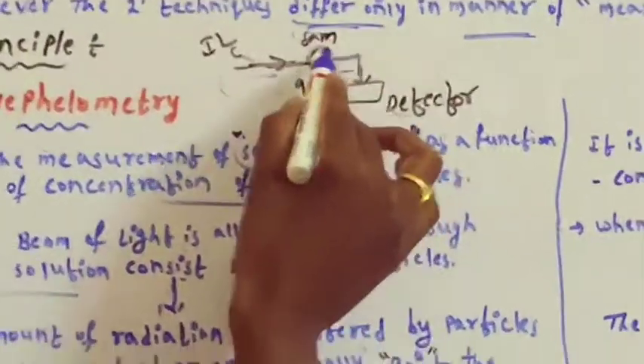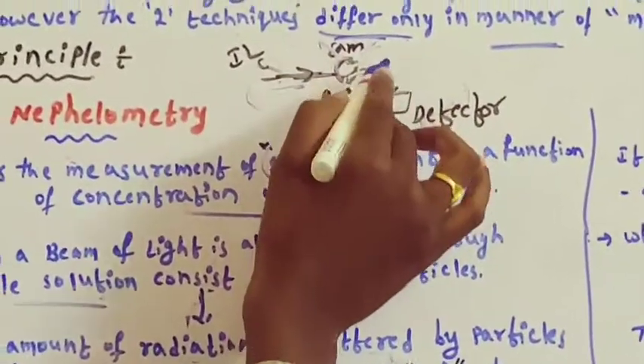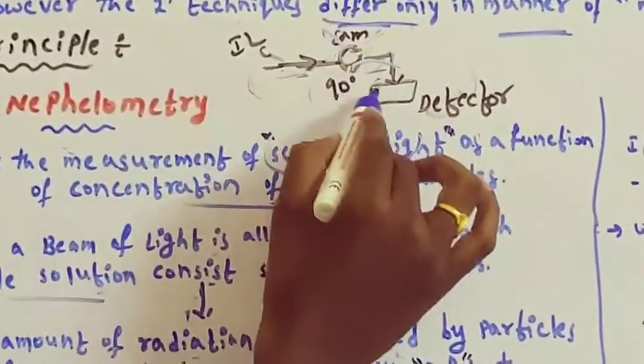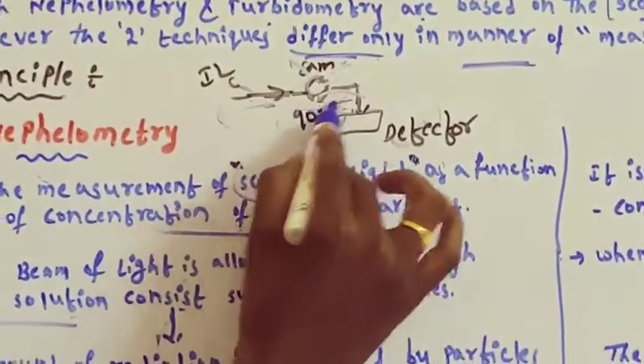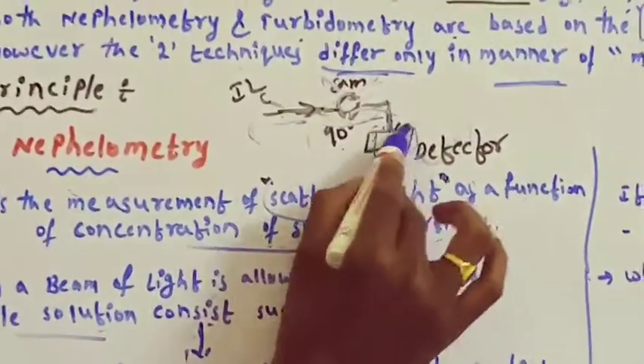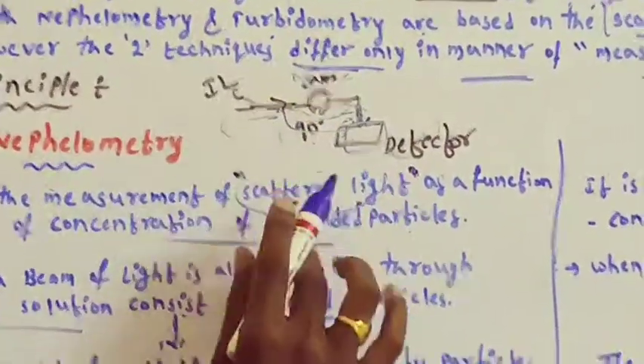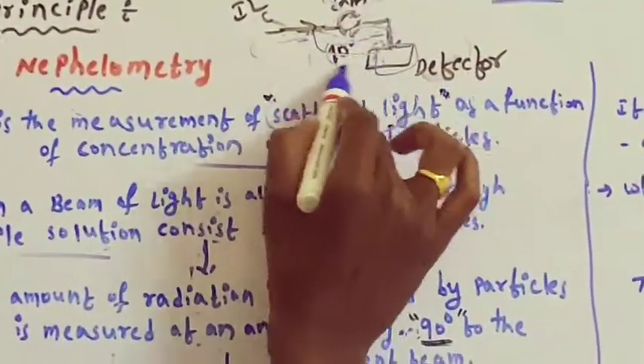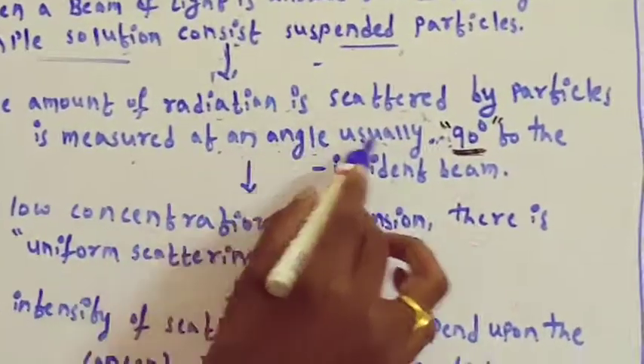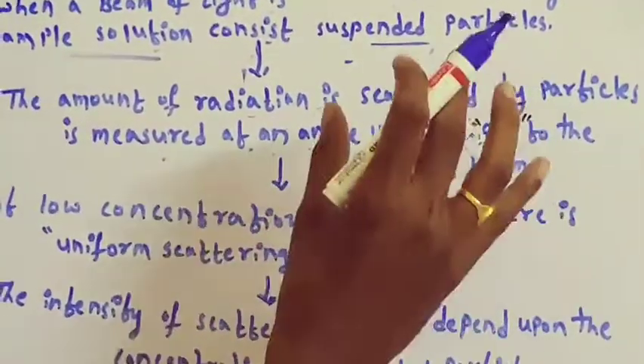The sample solution contains suspended particles. When radiation falls onto the sample cell, the suspended particles scatter the light. In nephelometry, the scattered light measurement takes place at 90 degrees to the incident beam — the detector is placed at 90 degrees to the incident beam. This 90-degree angle is very important.